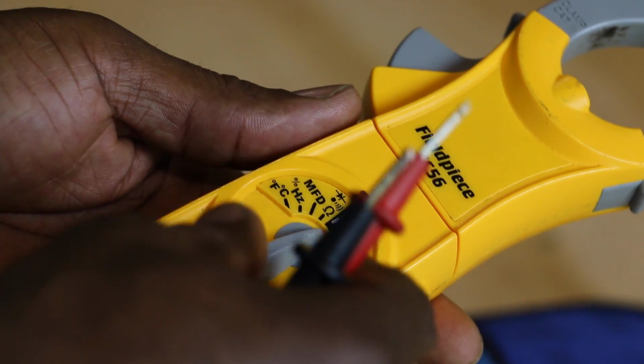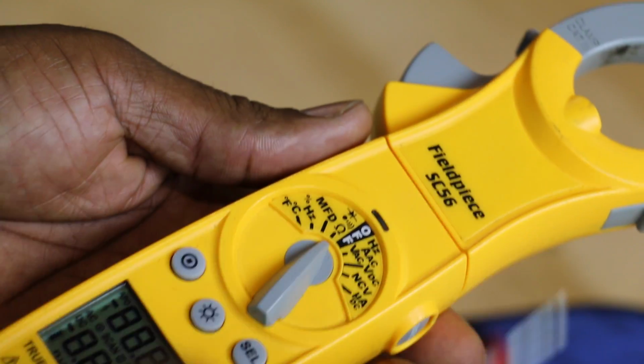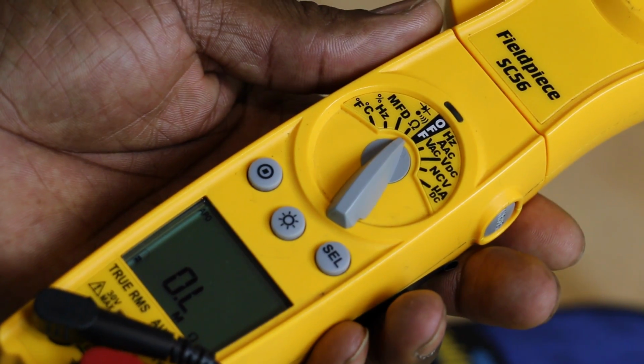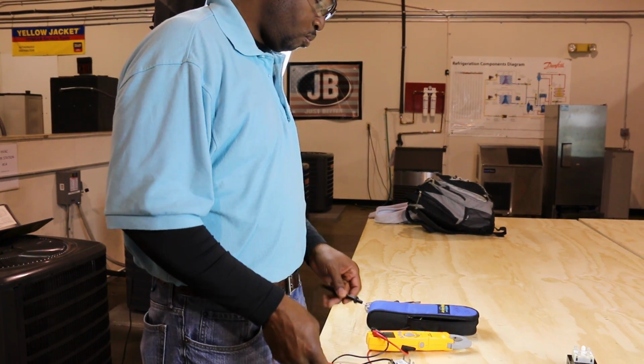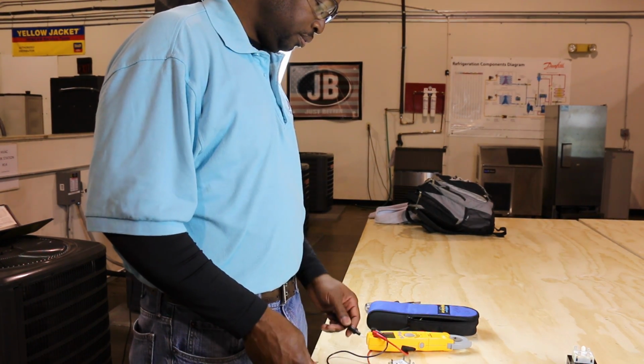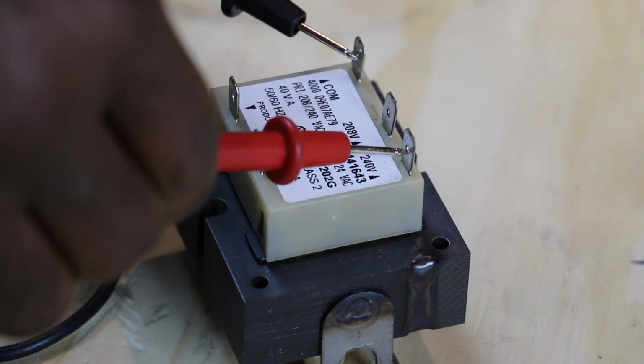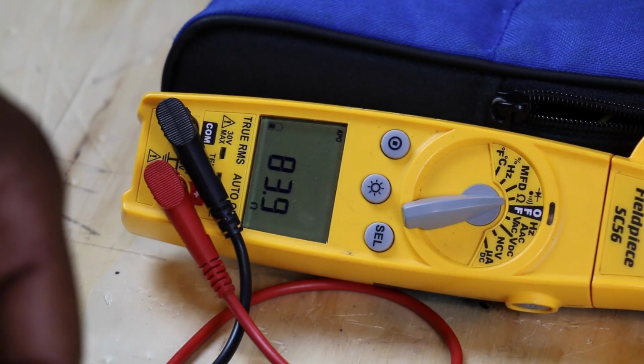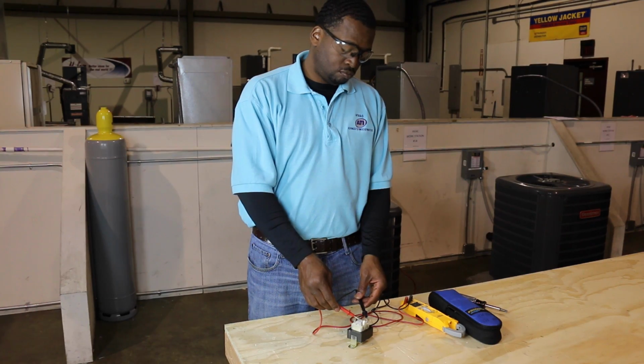The meter will be set to resistance so that we can measure the continuity of the primary and the secondary windings. First, Darren's going to measure the primary of the transformer. We want it to read some resistance, and depending on the transformer, the resistance can vary. In this case, it's right around 84 ohms.